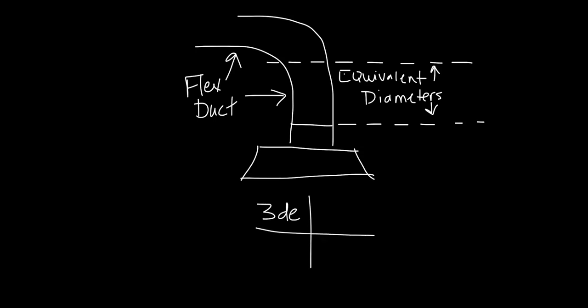What they found was that for the 3 equivalent diameter installation, the sound added ranged from negligible to only slight. Specifically, this type of installation added only 0 to 1 NC to the baseline or published data. As the distance of the straight duct shortens though, the sound increases. At 0 equivalent diameters of straight flex duct, the sound was found to increase between 6 and 9 NC.